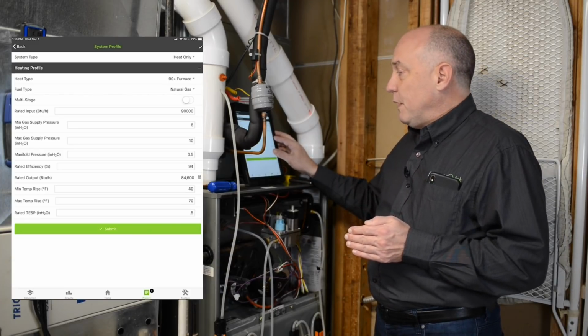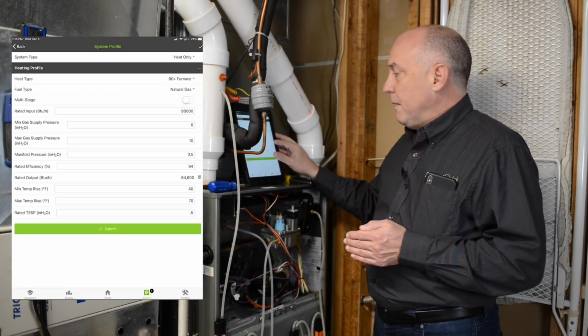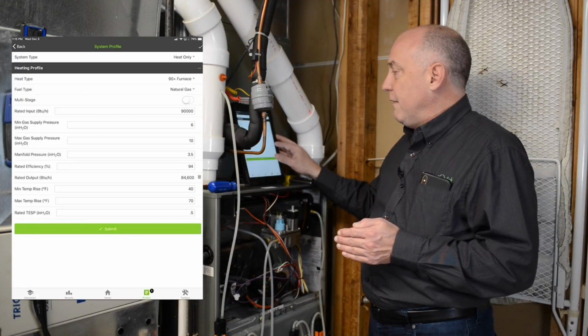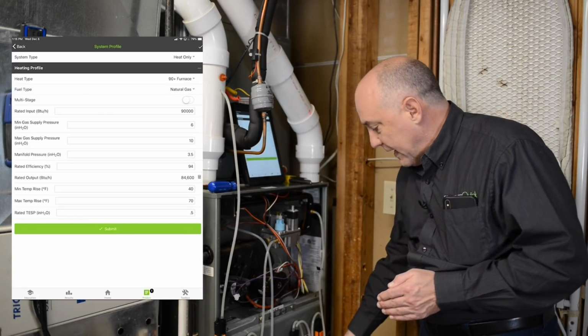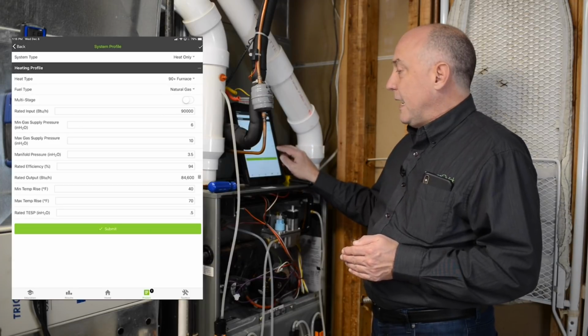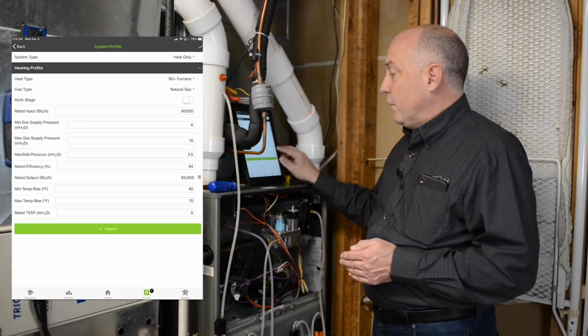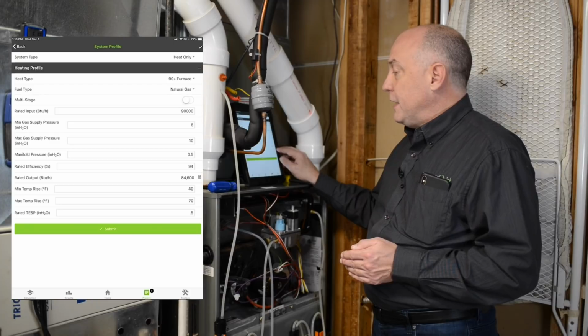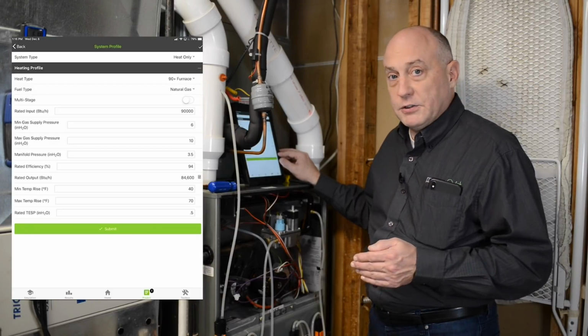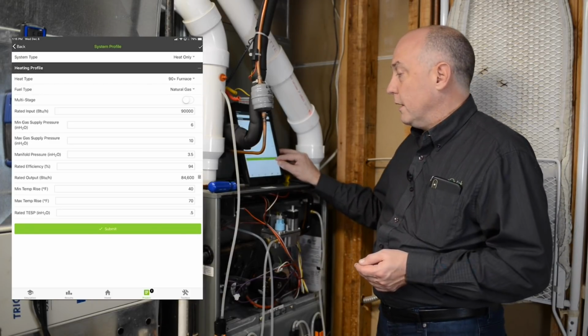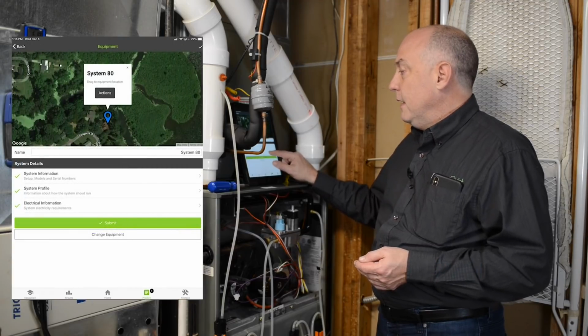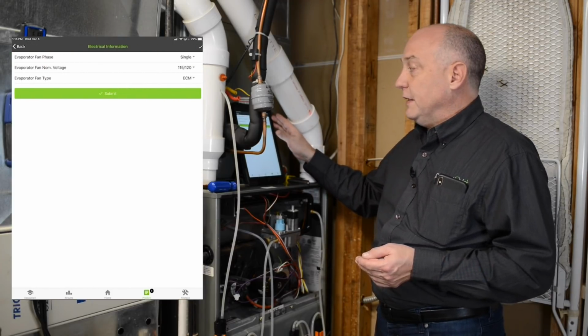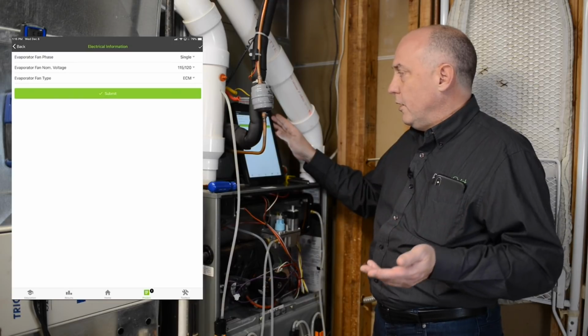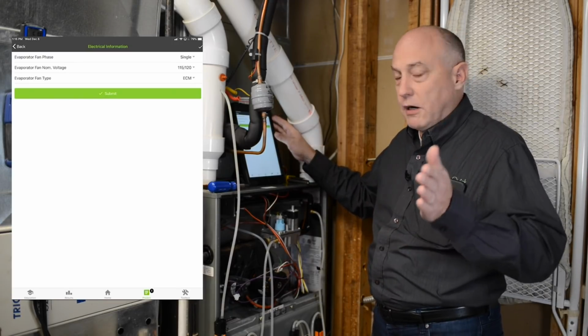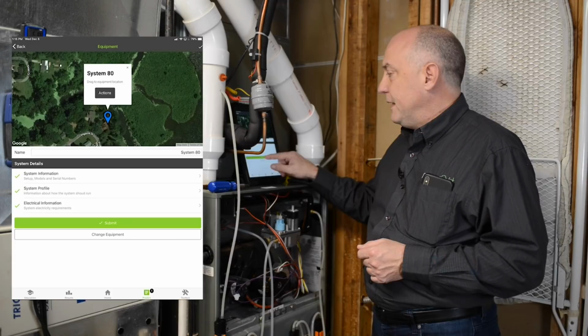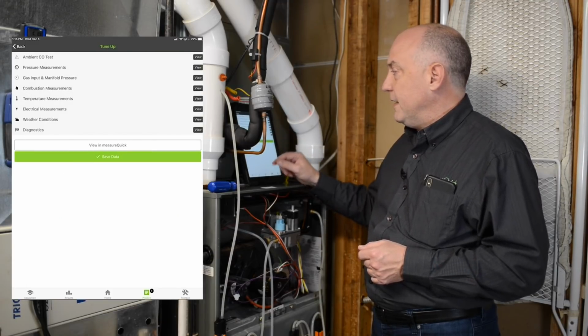I have my max gas pressure of 10 inches of water column, my nominal manifold pressure at 3.5, my rated efficiency I got down here off my tag at 94%. That calculates automatically my rated output at 84,600. I have my temperature rise from 40 to 70 degrees and my rated external static pressure at 0.5 inches of water column. So I'll go ahead and hit submit on that. Electrical information wise, it's a single phase evaporator fan. It's 120 volts and it's ECM, so I've got all that data in also. And at that point, I'm ready to take measurements and start my test.